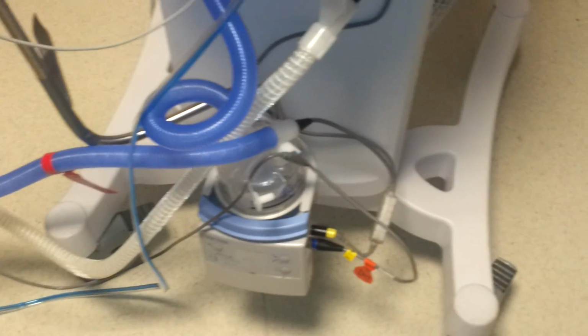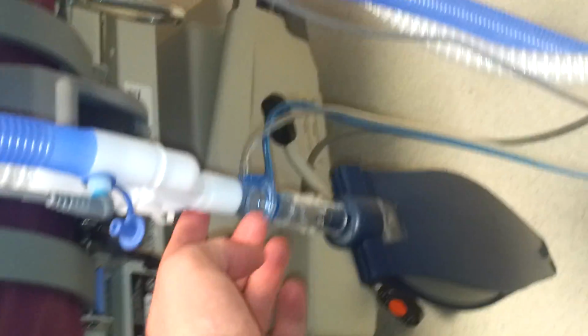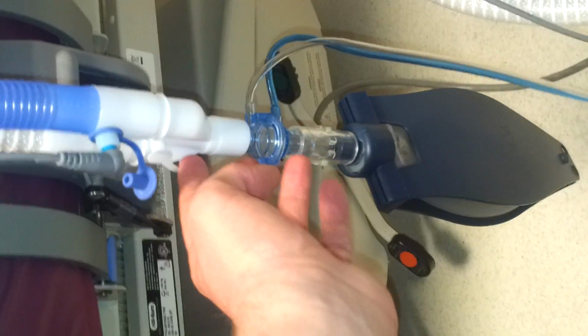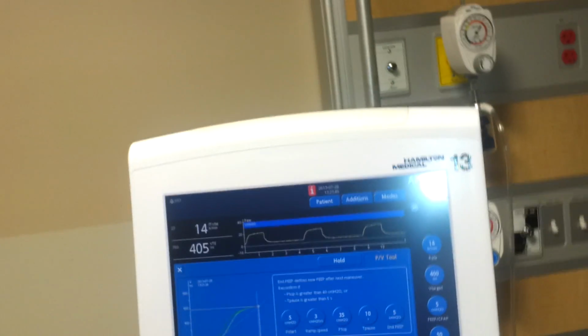Other than that, that's basically the main differences between this and some of the vents you'll see in New Brunswick. The circuit's pretty much all set up the same. Humidifier's the same. The only thing is the flow sensor at the end. We put our end tidal on the patient side of that, so on this side. And that's pretty much it.